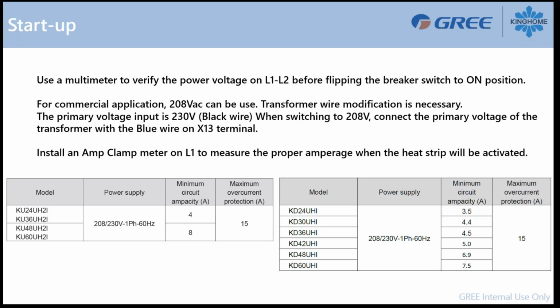Also, when you do your startup and you start up the fan, you can take the amperage with the clamp meter on your L1 and make sure the fan blower motor has the right ampacity. For the KU series, we have 2 different blower motors, one with a 4 amp ampacity, the other with an 8 amp ampacity. For the KD family, we have different blower motors regarding the tonnage. On this chart, you have the different amps we are looking for. Basically, the blower motor ampacity must be lower than the number you have on this chart.